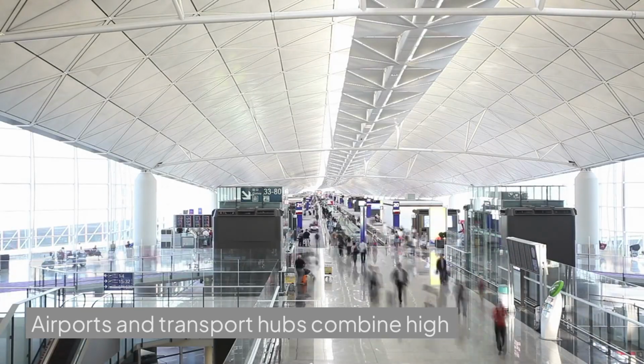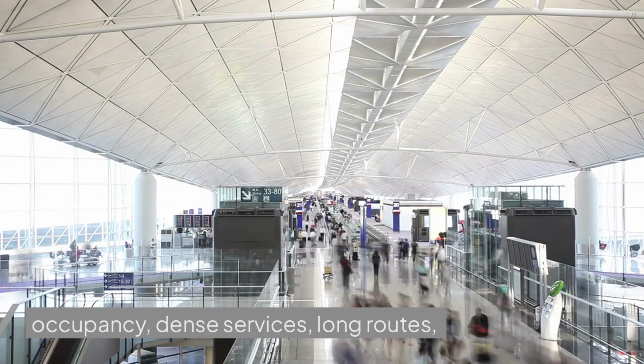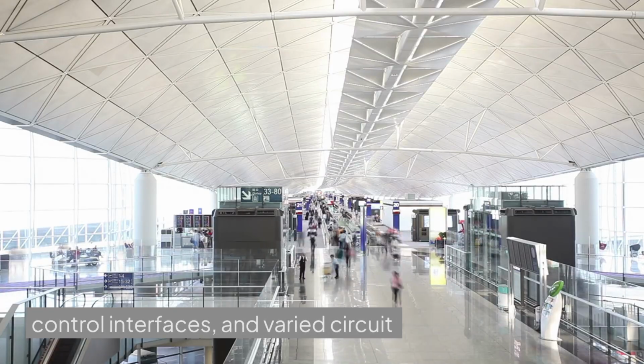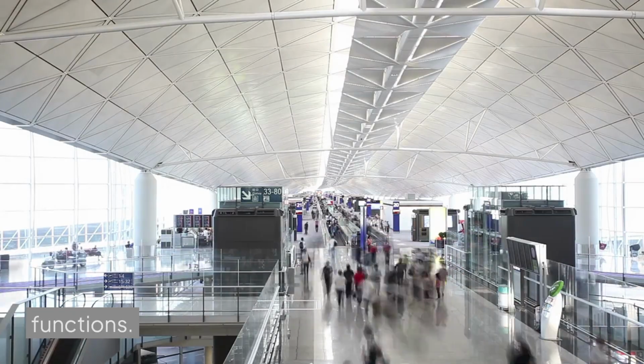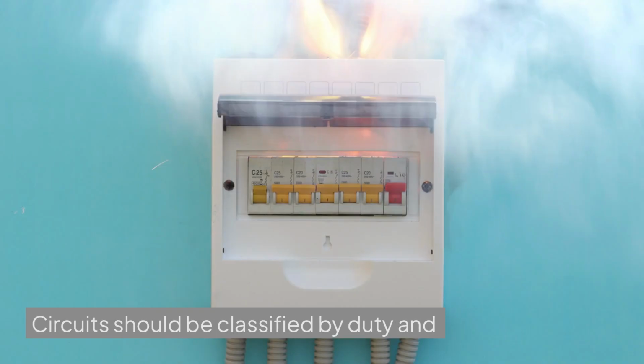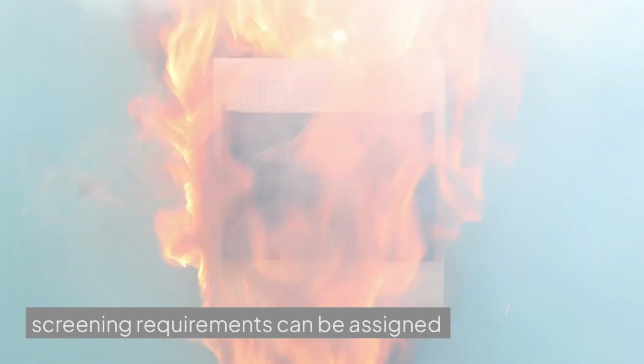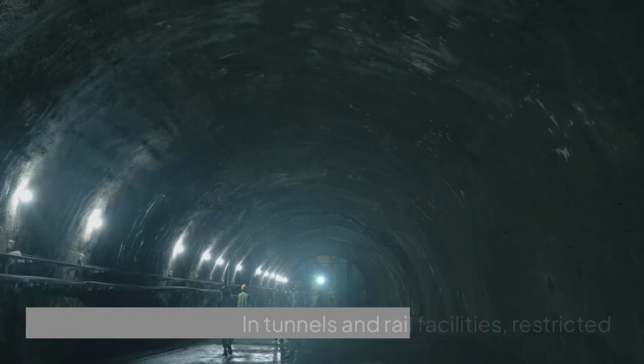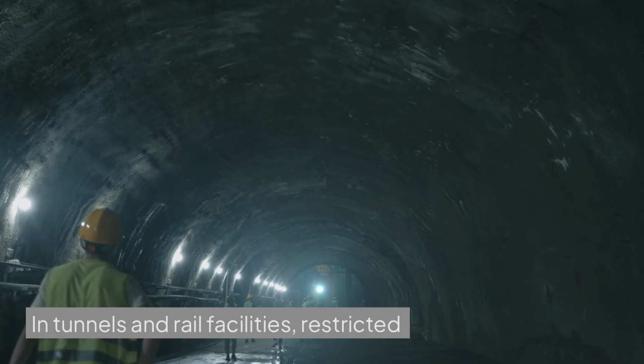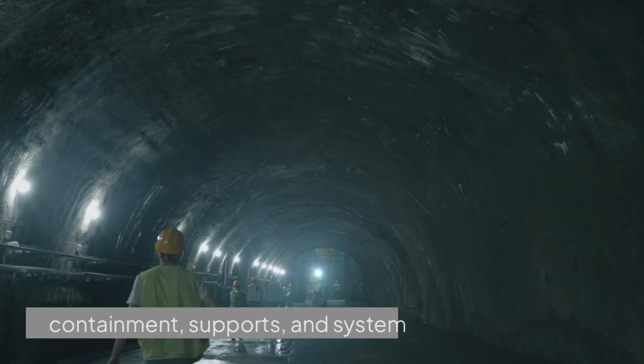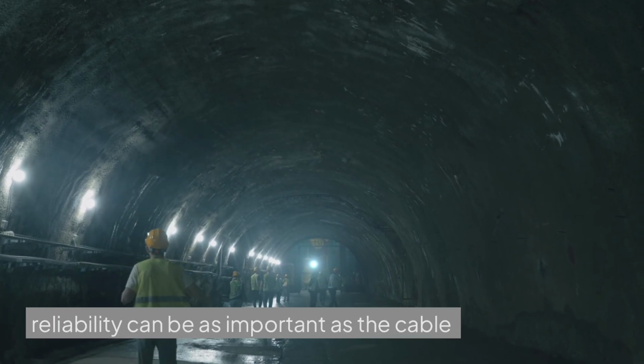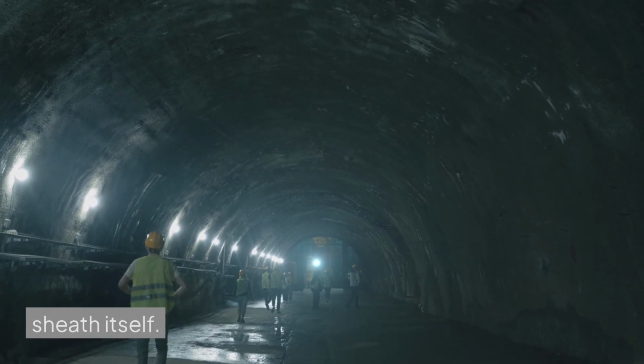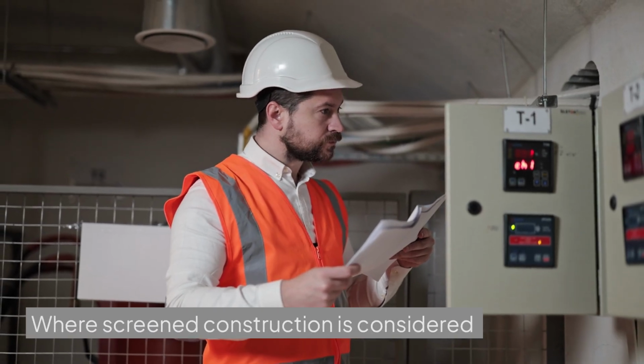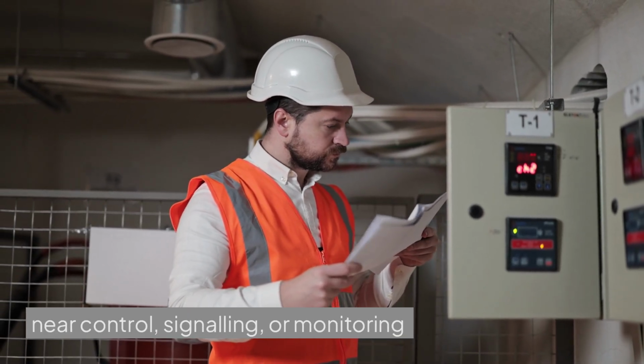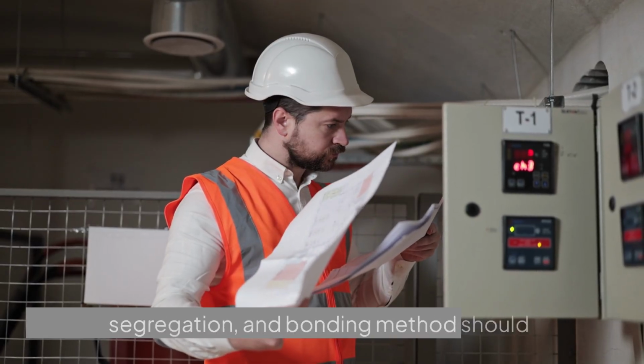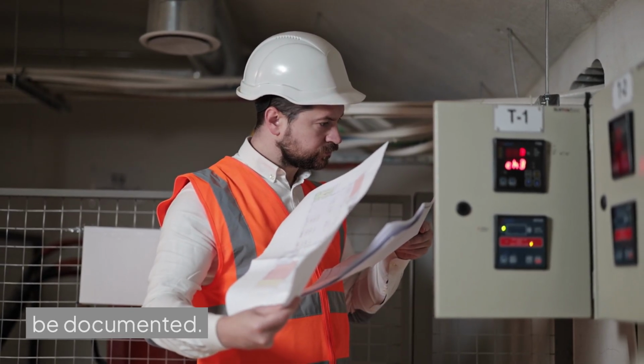Airports and transport hubs combine high occupancy, dense services, long routes, control interfaces, and varied circuit functions. Circuits should be classified by duty and route so that fire performance and screening requirements can be assigned deliberately. In tunnels and rail facilities, restricted egress, smoke, maintenance access, containment, supports, and system reliability can be as important as the cable sheath itself. Where screened construction is considered near control, signaling, or monitoring systems, the interference concern, segregation, and bonding method should be documented.